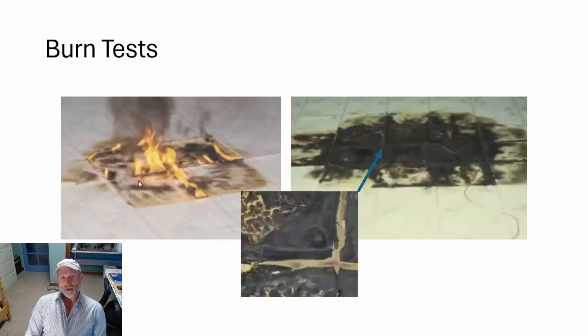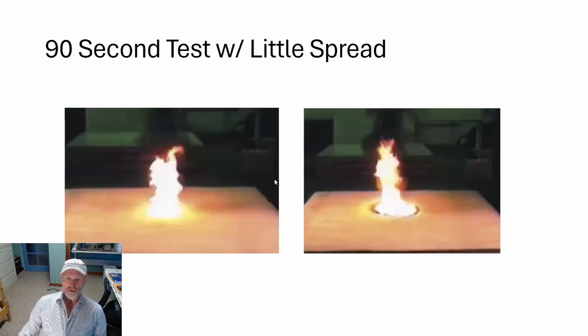So here's an example of a fuel fire on tile flooring. What's interesting here is the tiles will actually start to curl up, and you can see a close-up view of this from fuel, but the irony is you're going to see similar results from a cardboard box or a pallet or some kind of wood. Obviously, you'd have some debris there if it was a pallet, but depending on the severity of a fire, it's easy to mask the results from a liquid fuel fire. And this is the kind of scenario where you do have to do further tests. So this is a non-porous surface.